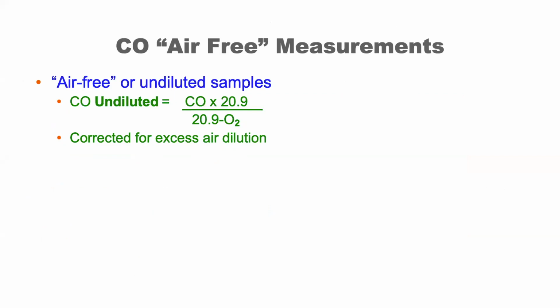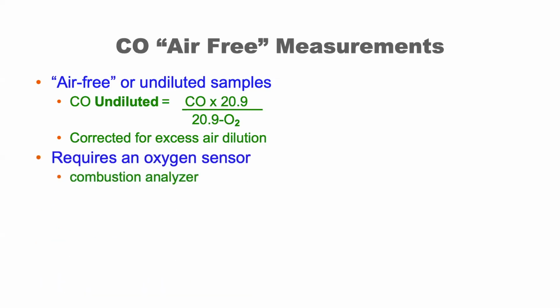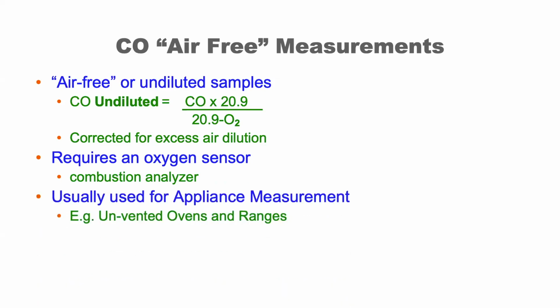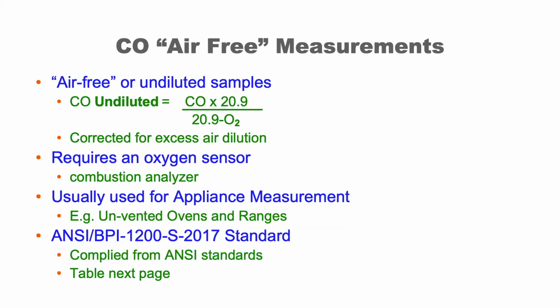So we did mention we'd be talking about CO air-free, and that would be undiluted CO. You can mathematically undilute it by taking a ratio between CO and the amount of oxygen or the amount of CO2. Again, the calculation goes the same way. This corrects for excess air. This requires a combustion analyzer with either an oxygen or a CO2 sensor. And usually it's used in appliance measurement, but more and more it's becoming used in stack measurements.